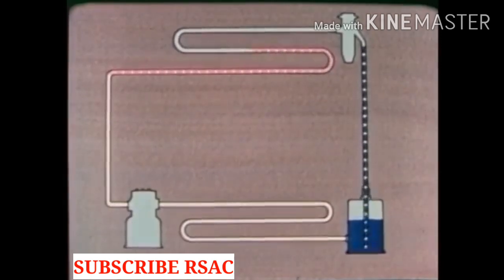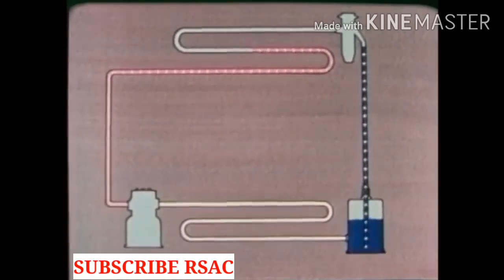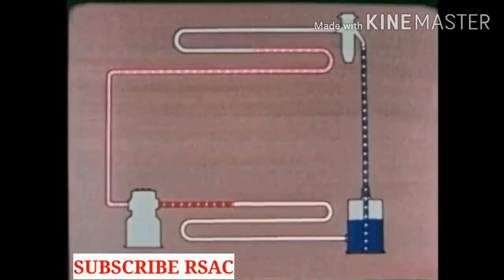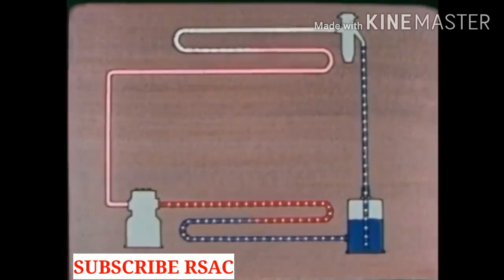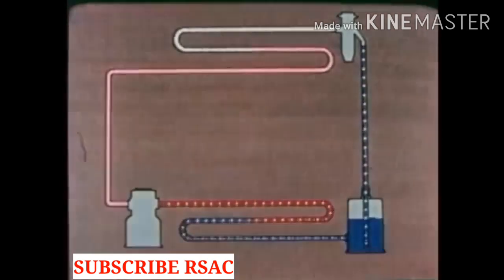Remember, any substance must take in heat in order to change from a liquid to a gas. The compressor sucks the vapor out of the evaporator and compresses it. This increases the pressure and temperature. The vapor is now hotter than the surrounding air. So in the condenser heat is given off to the air. As the refrigerant loses its heat it changes from a gas to a liquid and flows into the receiver.